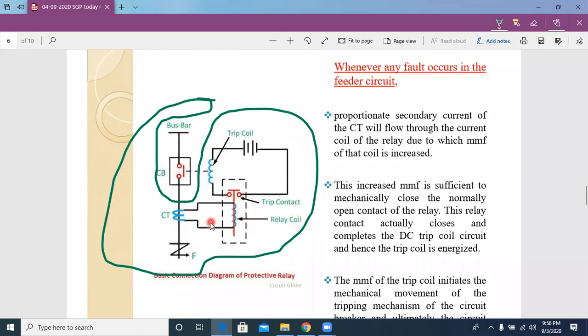In this case the activating quantity is current, and that's why we place a current transformer to monitor this particular line current. That current transformer secondary is connected to the relay coil and the tripping contact. When the relay coil is excited, due to the excitation the trip contacts are operated. I repeat once again, the trip contact action depends on the excitation of the relay coil.